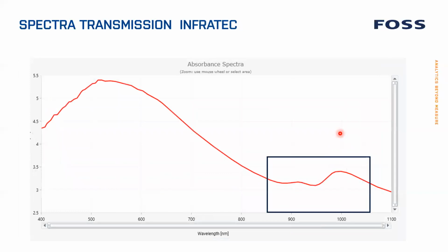If we then instead look at an Infratec, this is very high absorption also. This is actually so much so you can't see through it at all. So this is totally black. So this is the limitation of the instrument, and 5.5 absorbance units is really, really dark when you compare this to what we had before when we were below 1, which is very far down.